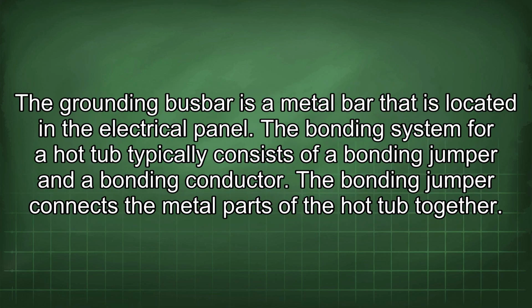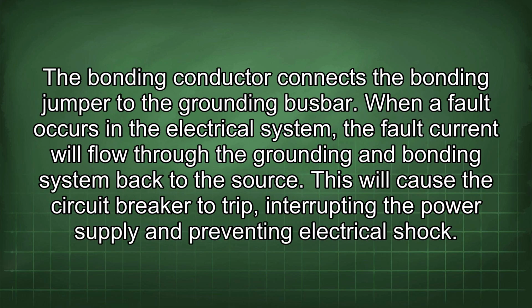The grounding bus bar is a metal bar that is located in the electrical panel. The bonding system for a hot tub typically consists of a bonding jumper and a bonding conductor. The bonding jumper connects the metal parts of the hot tub together. The bonding conductor connects the bonding jumper to the grounding bus bar. When a fault occurs in the electrical system, the fault current will flow through the grounding and bonding system back to the source. This will cause the circuit breaker to trip, interrupting the power supply and preventing electrical shock.